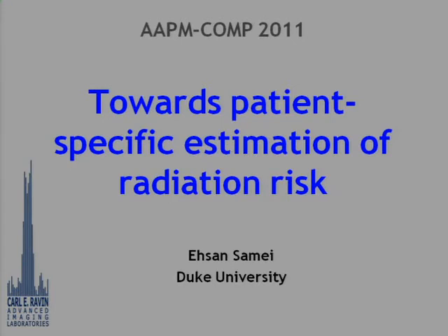My question has to do with the dose medium. With CTDIvol, we're talking about dose in air. So when we go to these other models, are you computationally taking into account the composition of the tissue? Absolutely. We are talking about absorbed dose in tissue, and not in water. Yes, absolutely. Good question.